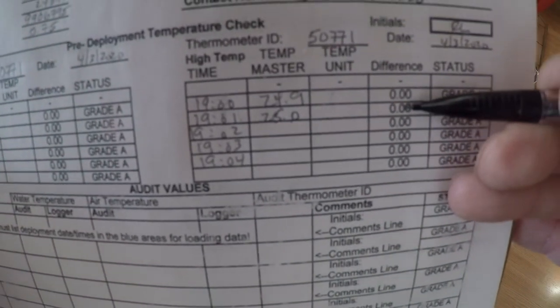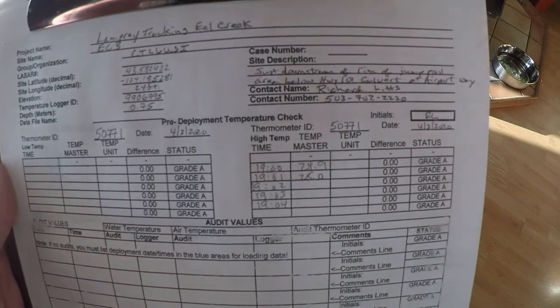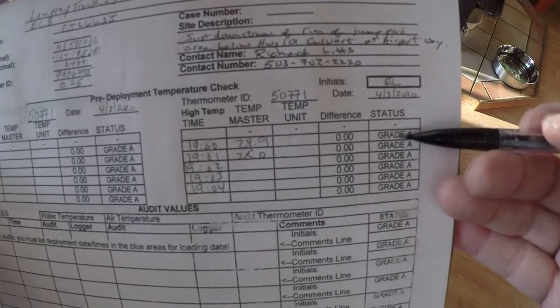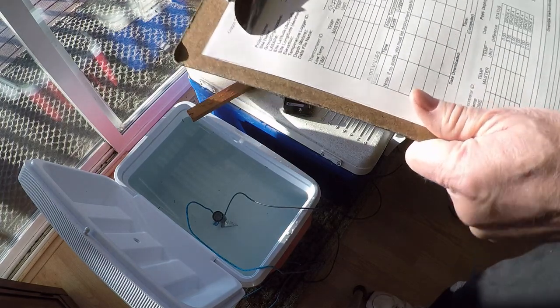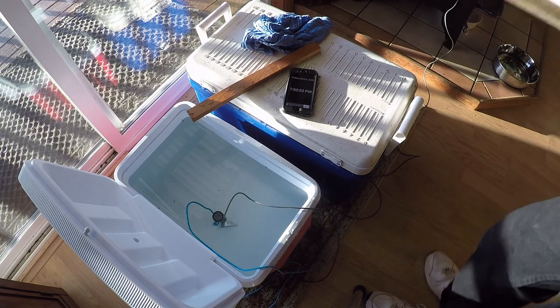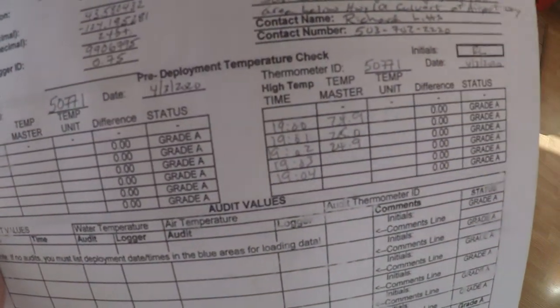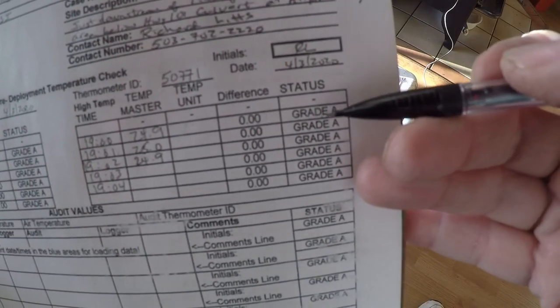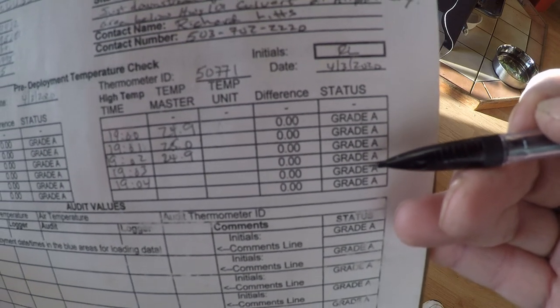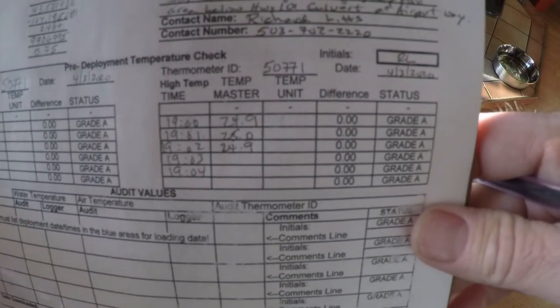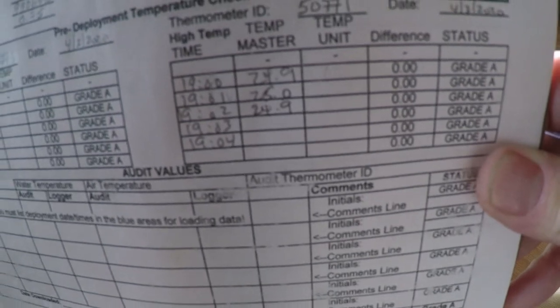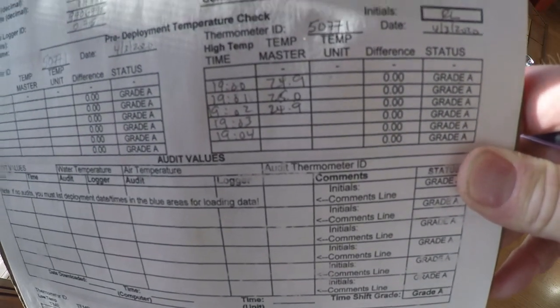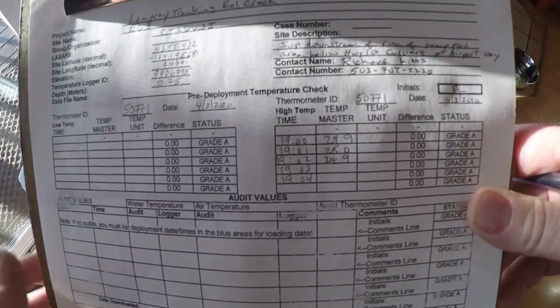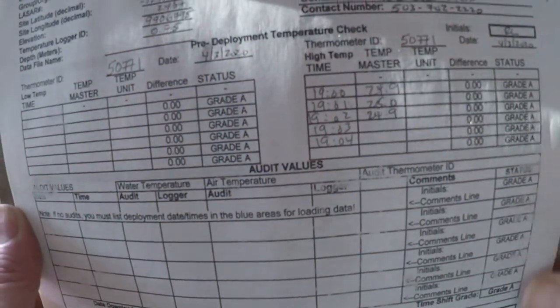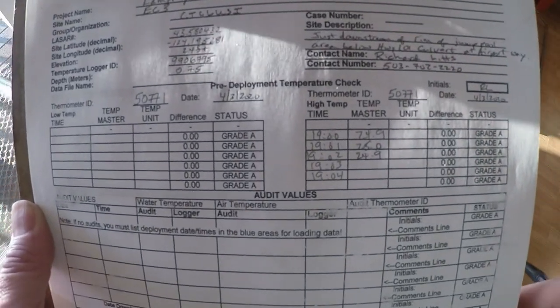Then the next thing we'll do is calculate the difference. This whole form is actually a piece of software that you can use, and it'll calculate that difference and then grade your answer. We've got 7:02 now, reading, and we're at 24.9. I wrote that here in this third column, and eventually we're looking for this status to be a grade A, which means that the difference between our probe and the NIST digital thermometer is less than 0.5 degrees centigrade. So that's what we're trying to make sure, that our continuous temperature probe is reading within half a degree of the NIST thermometer.